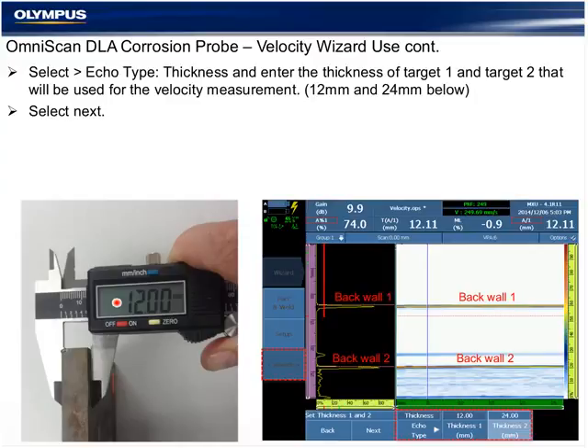That is the only way to get a new velocity other than carbon steel into the default setup files that come with the probe. Once the wizard steps are done with the new velocity, it adjusts the scale, it adjusts the UT axes, and the readings are then in tolerance with the new velocity. And again, there's a separate section within the presentation material you'll receive regarding each of the sensitivity, wedge delay, and velocity measurements, but keep it very simple.